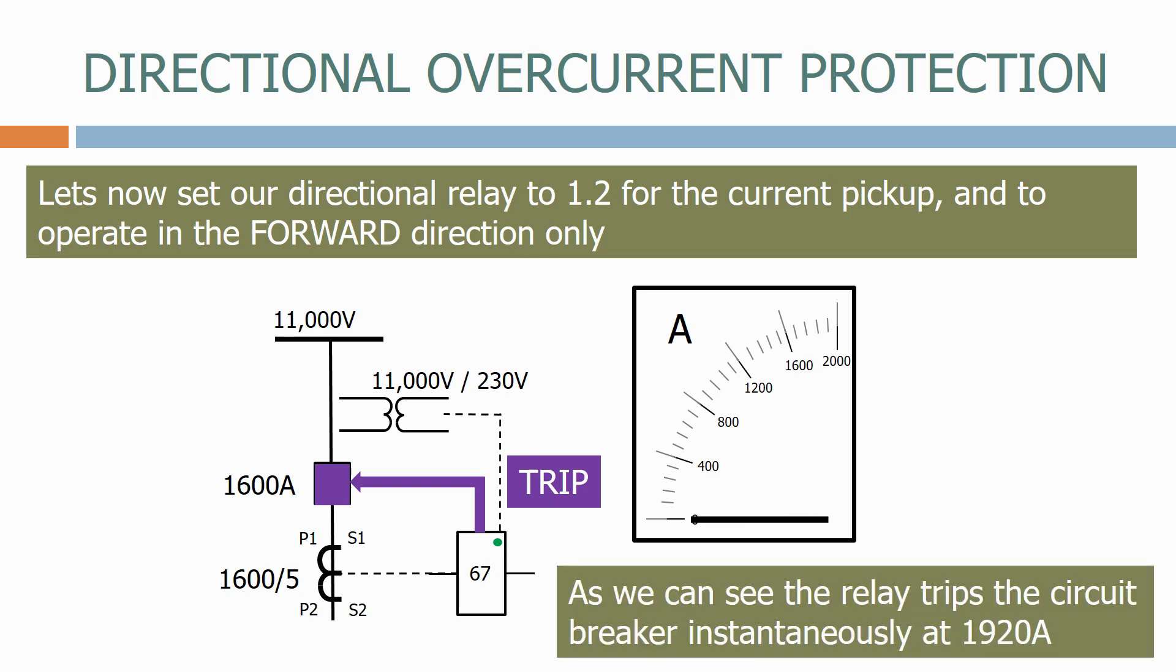As we can see, the relay trips the circuit breaker instantaneously at 1920 amps.